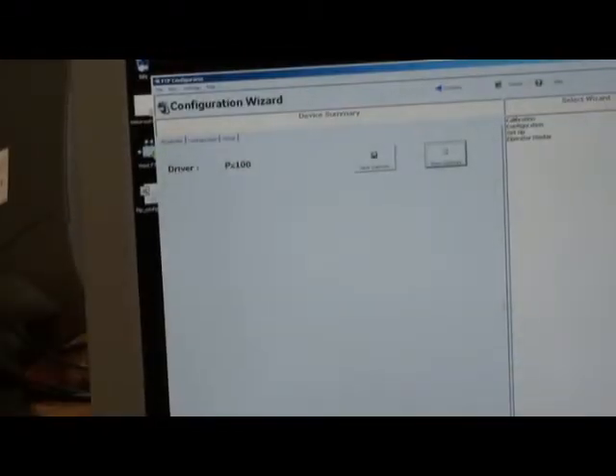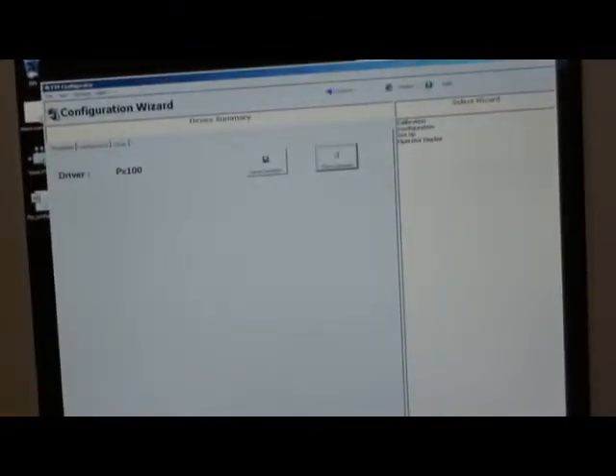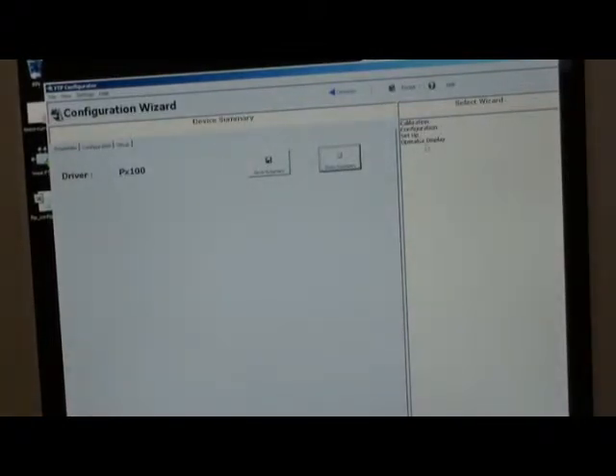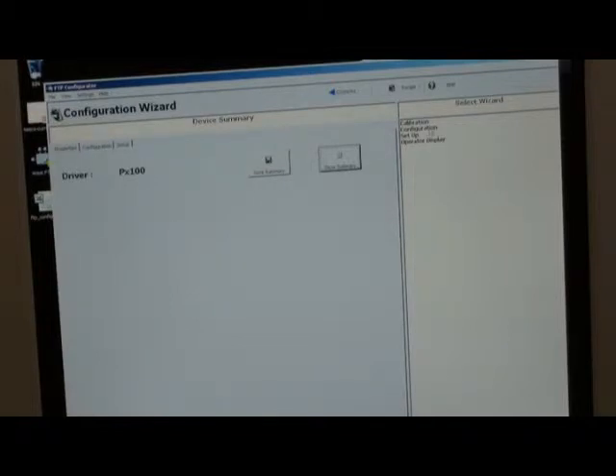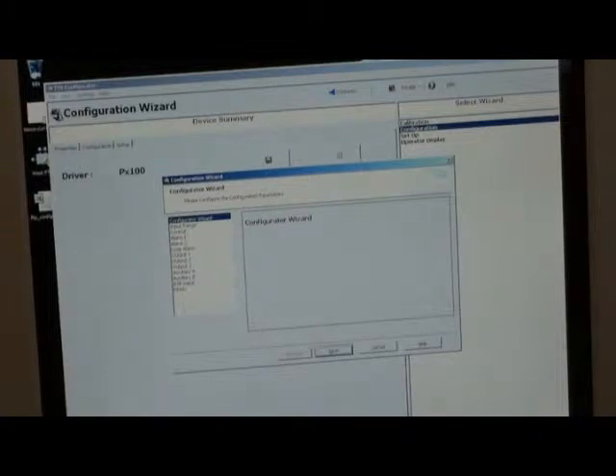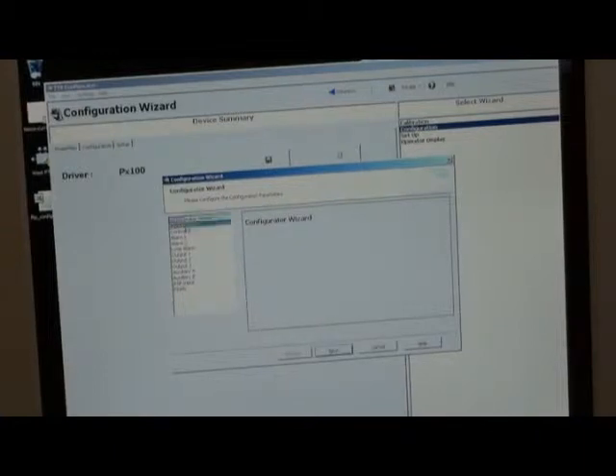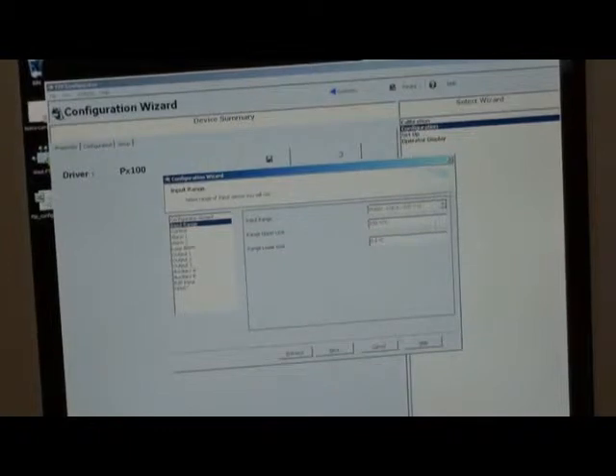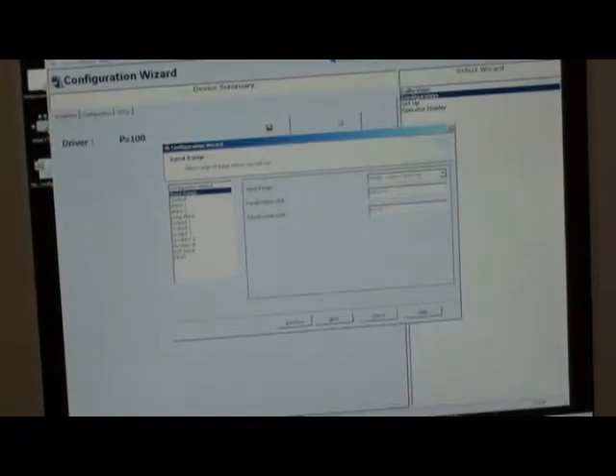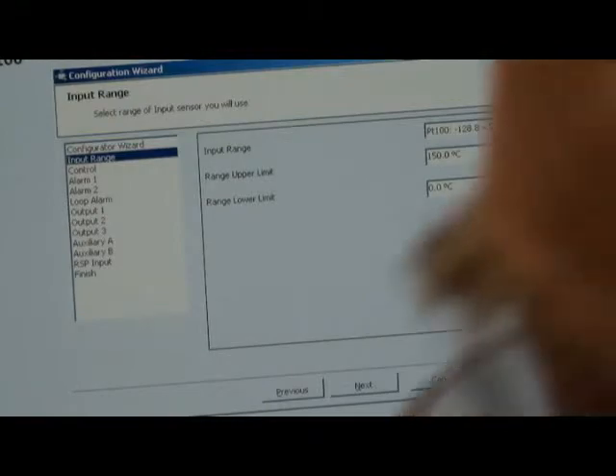Now let's go to the wizard for configuration. We've got four wizards: calibration, configuration, setup, and operator display. So we want to configure. Select the configuration menu, and this is the configurator wizard. First of all, input range. This is our range limit: 0 to 150 degrees C. So if I go to the controller first of all, if I was doing it from the front of panel.